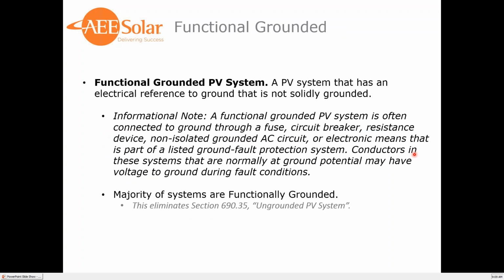So one of the biggest changes in the NEC 2017 was the functional grounded. Previously we would say transformerless inverters were ungrounded and transformer inverters were grounded. Now they have made the change that essentially they operate the same. And actually, a very small amount of the inverters that we've used have actually been grounded. So now there is no difference between the two in the code, which will simplify things for your inspector.